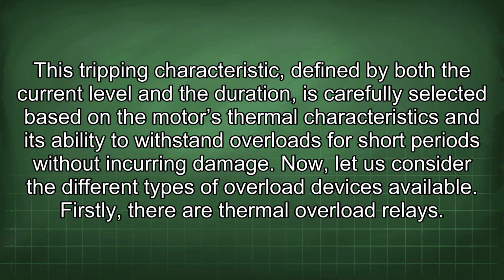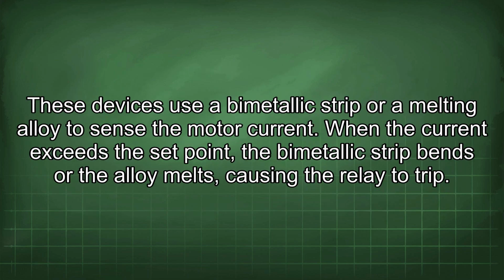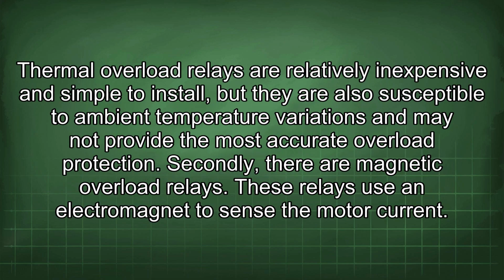Now let us consider the different types of overload devices available. Firstly, there are thermal overload relays. These devices use a bimetallic strip or a melting alloy to sense the motor current. When the current exceeds the set point, the bimetallic strip bends or the alloy melts, causing the relay to trip. Thermal overload relays are relatively inexpensive and simple to install, but they are also susceptible to ambient temperature variations and may not provide the most accurate overload protection.